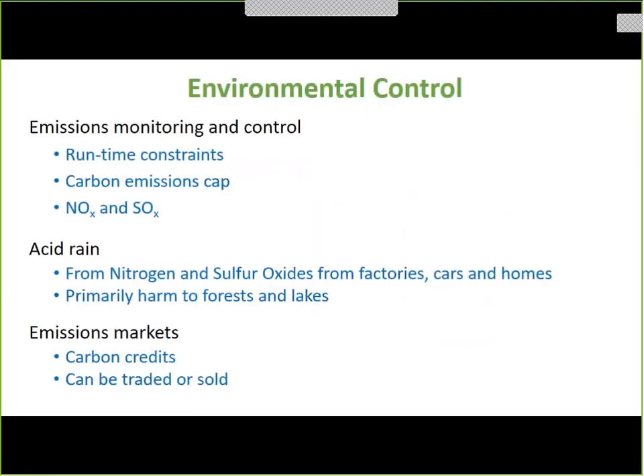Okay, let me try to wrap up since we're already over the hour. Environmental control, all right. One of the big ones is backup generators. We have a gas diesel generator for ECE. You can't run it 24 hours a day. You get in big trouble because you're polluting the air. So you're only allowed to run a diesel engine a certain amount of time per year. So you have to live with that constraint.